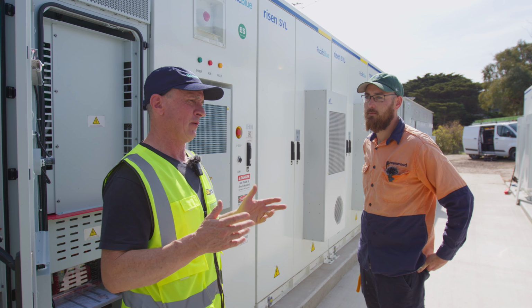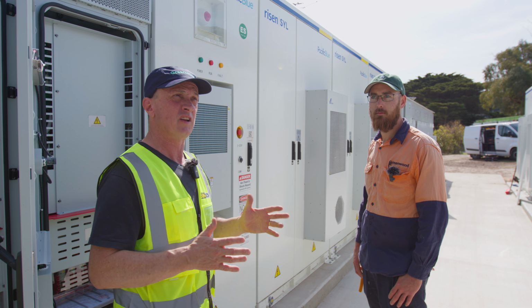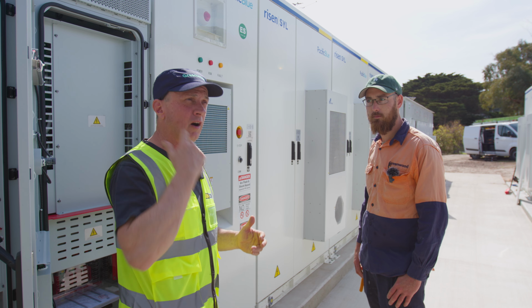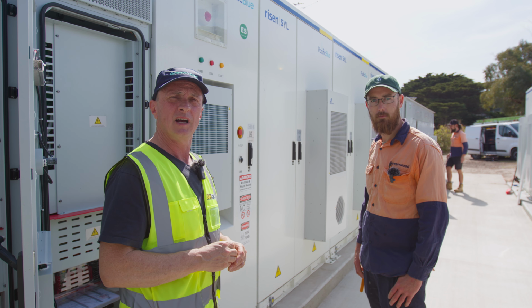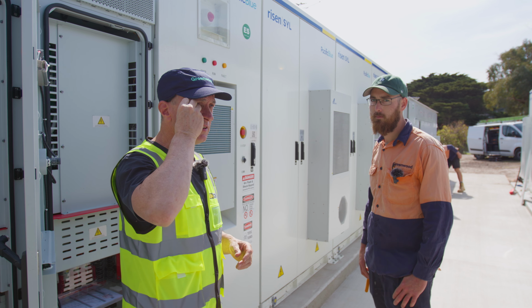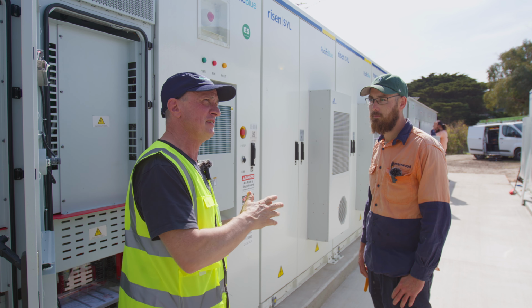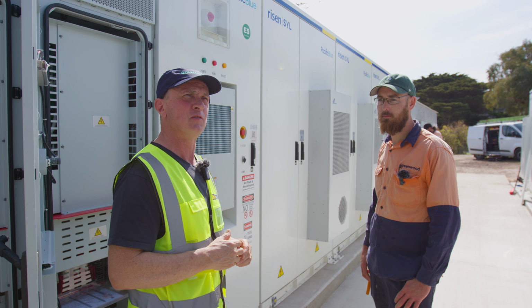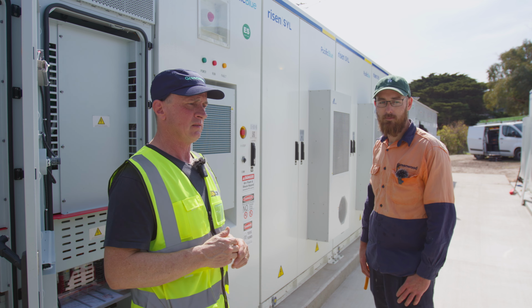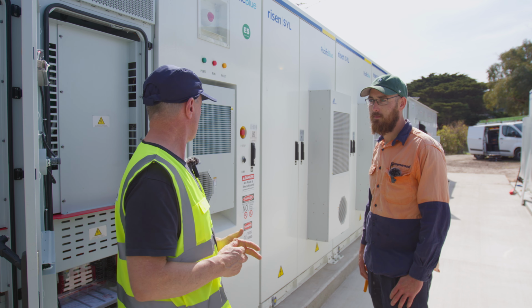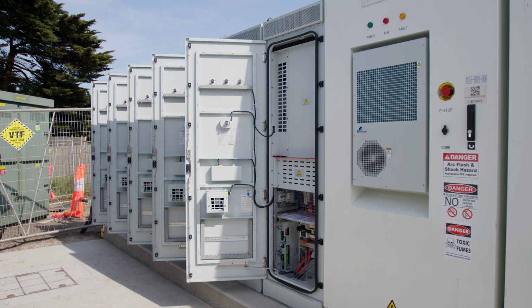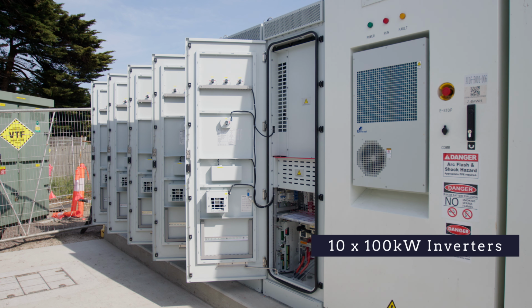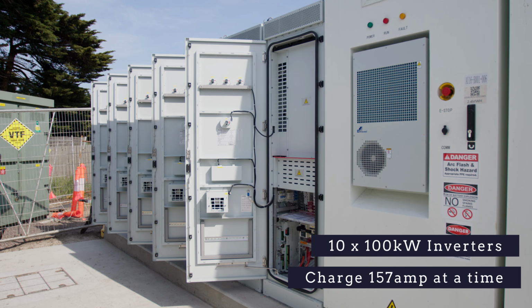Okay, so we're here at the inverter station section of this particular project. We're talking about a BESS system. We're talking about 10 inverters. Alex did correct me, I said 8 before, but there's actually 10. Now, just tell us about these inverters, Alex. What are their specs? Well, these inverters are 100 kilowatt each. They are capable of charging the batteries at about 157 amps at a time. So there's a lot of power that can be pushed through 10 of them, through to these batteries.